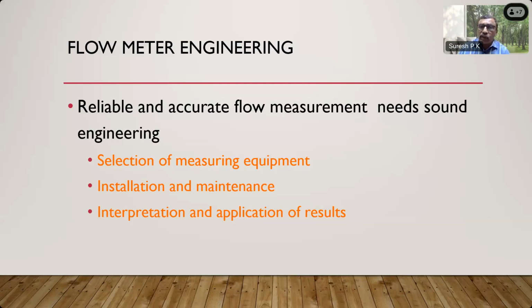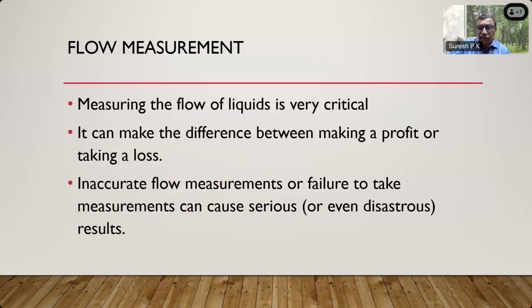If a flow meter shows a bad reading one fine morning, you don't suddenly change or repair the flow meter. It may be due to some errors which have happened unknowingly, or due to some foreign content passing through it or something like that. So application and interpretation of the results is also important. That needs experience. There is no better person than the people who are working in the plant, who can interpret the results and apply them for better accuracy.